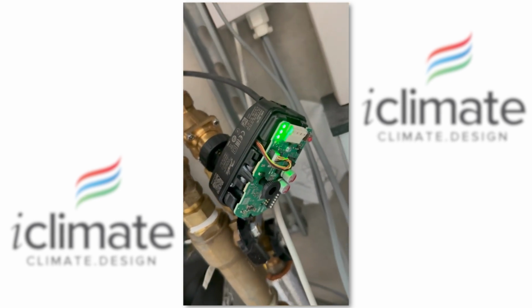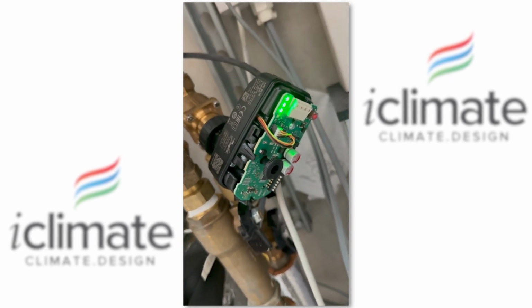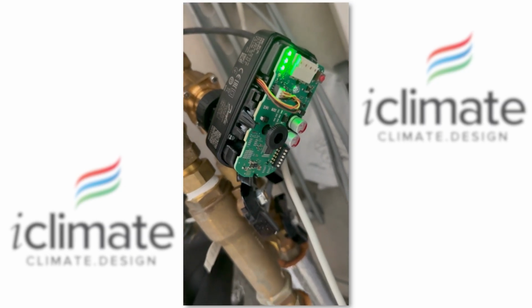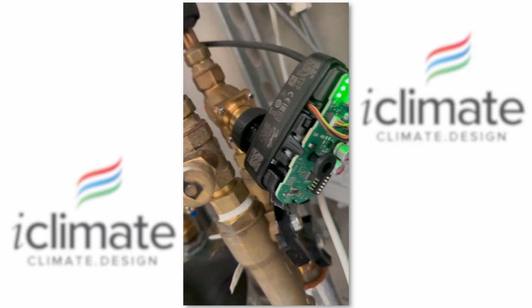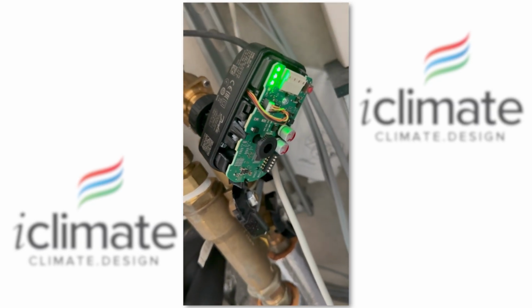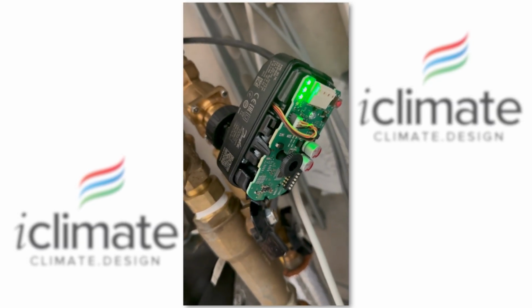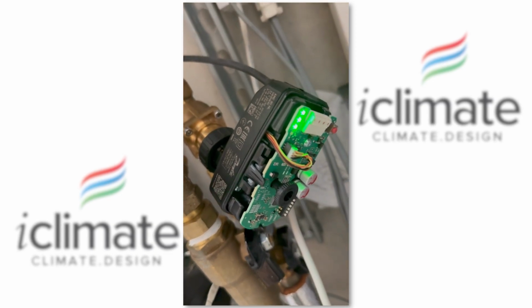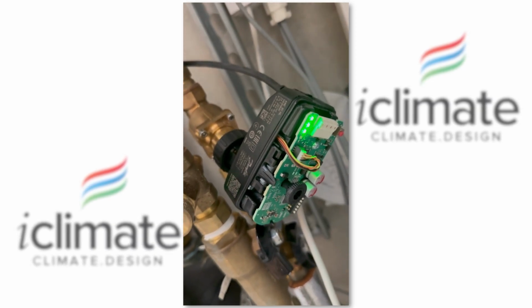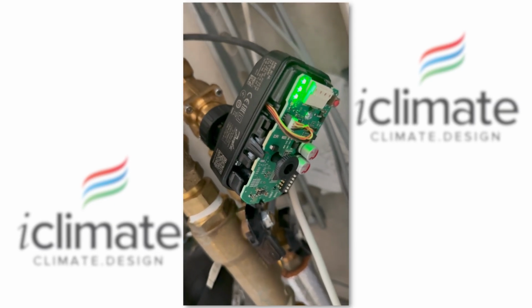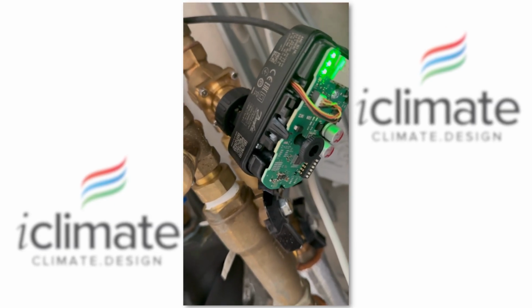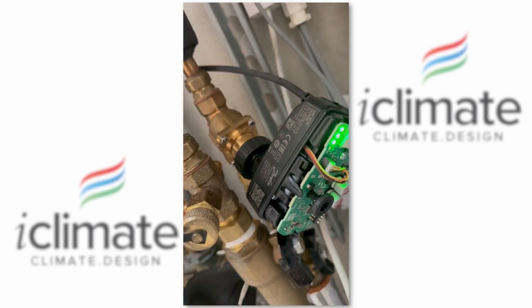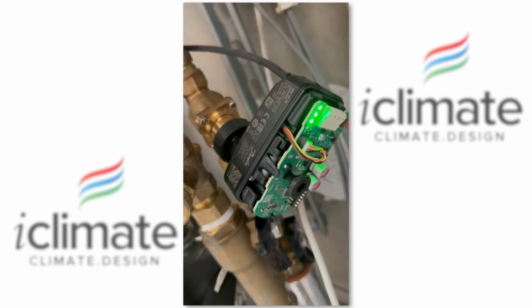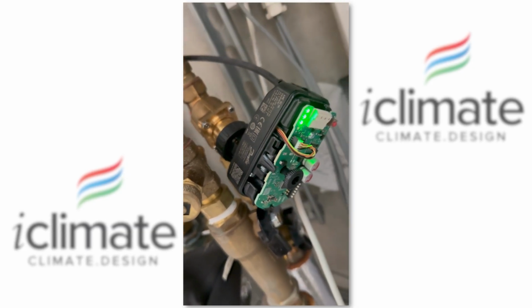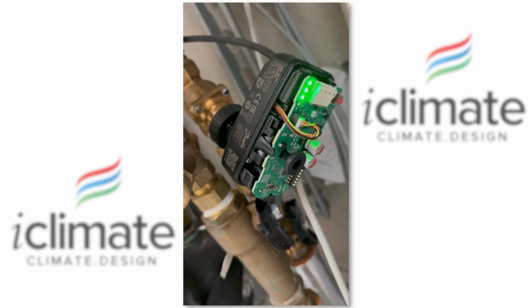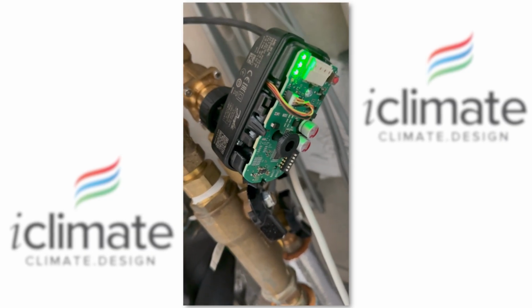And now we're going to turn the fan coil unit off and watch the actuator step itself back off, and then verify there's no heating flow through the PIC valves. The reason we're verifying the flow is because we had on site existing stiff PIC valves that possibly had debris inside, and we're just causing too much resistance for our set of actuators. And when you have that, the torque rating goes through the roof that is required to mechanically drive the spindle or release the stem, and then you can damage your actuators, which is the situation that we had, but we replaced them with another set of actuators we had. So let's go turn it off and verify flow and watch the valve close.